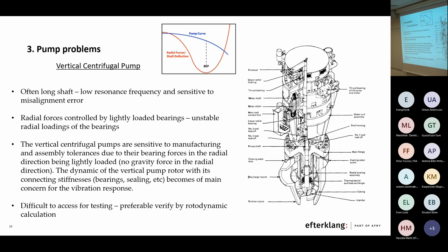It depends on the shaft deflections here. So if you're not operating your pump at an optimum point here, where you keep your radial forces and shaft deflection as low as possible, then you will have increased your vibration. So that's why it's so important that, when dealing with pumps and vibration, you must look into your hydraulics situation.